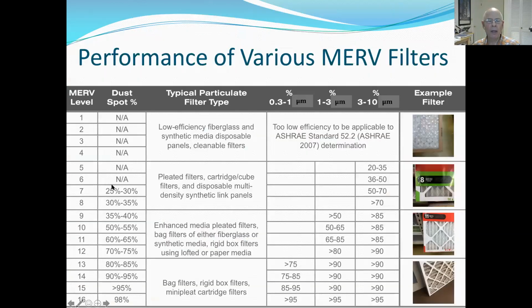It's very small. So let's go down to the MERV 13 line that I told you about. It's on the left-hand side, close to the bottom of the chart. Follow your eye across this chart from MERV 13. Go to the right, and you'll see that in the 0.3 micron range, greater than 75% removal from this filter. As you get into the larger particles, remember it was 2.5 to 10, as you get into the larger ones, you get over 90% removal. That's why we're saying make sure you have a MERV 13 or minimum filter. You can see at the smaller ranges, sometimes you don't even have a measurement value for the smaller particles, or it gets much, much lower in terms of removal.